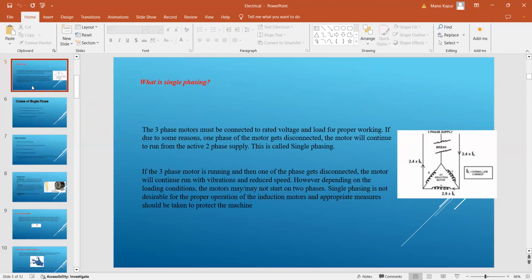Very good. It will take more current and the motor is going to heat up. And plus your pressure in the gauge will be less, right? Because it is revolving at the reduced speed, right? Yes, sir, it is. Very good. And you are going to feel some vibrations also. However, depending on the loading condition, the motor may or may not start on two phase. That is what I said. It depends on your luck. Single phasing is not desirable for proper operation of the induction motor, and appropriate measures should be taken to protect the machine from single phasing.